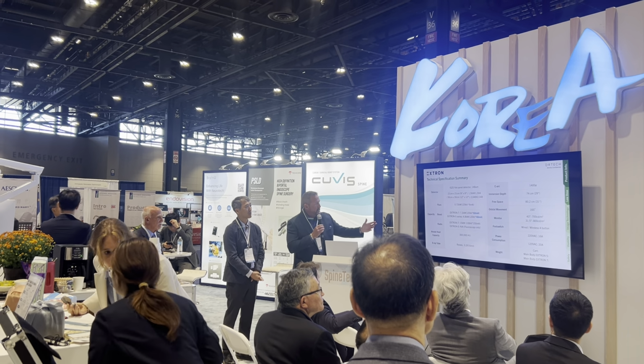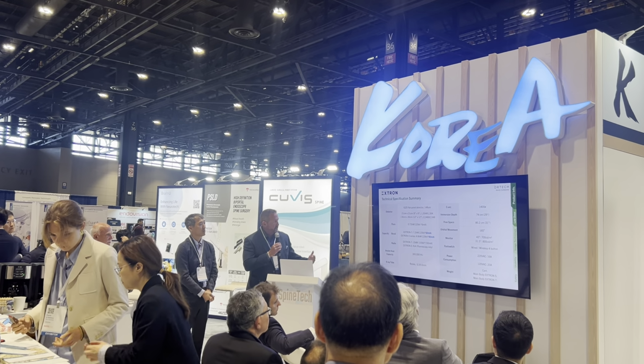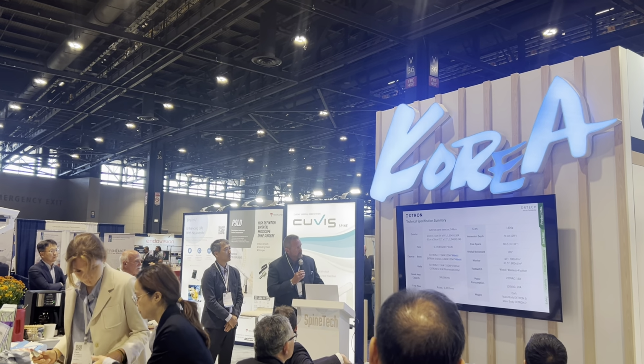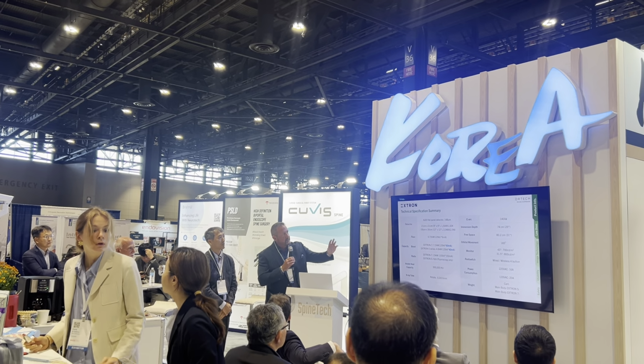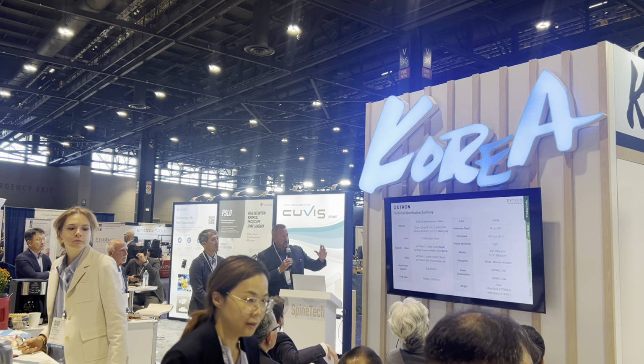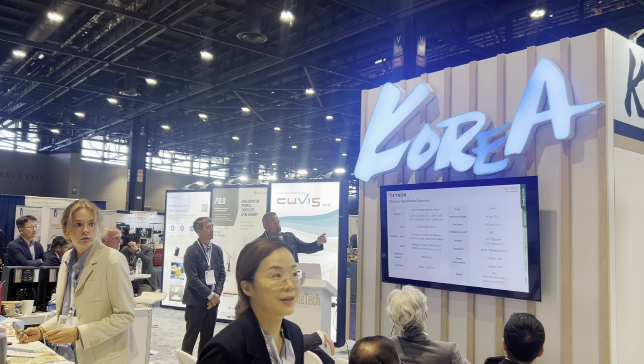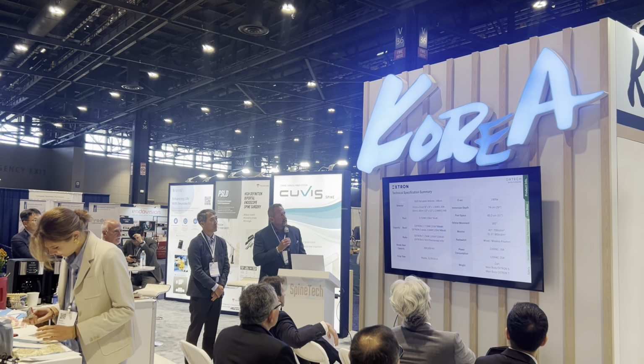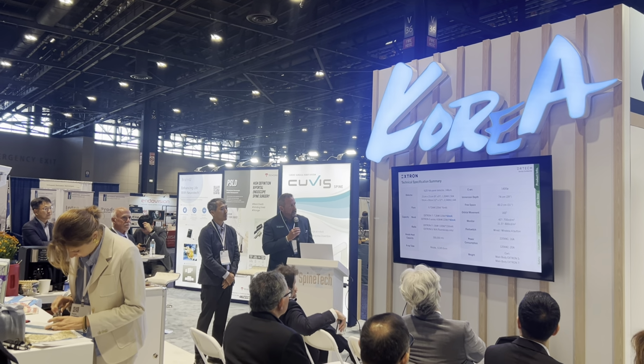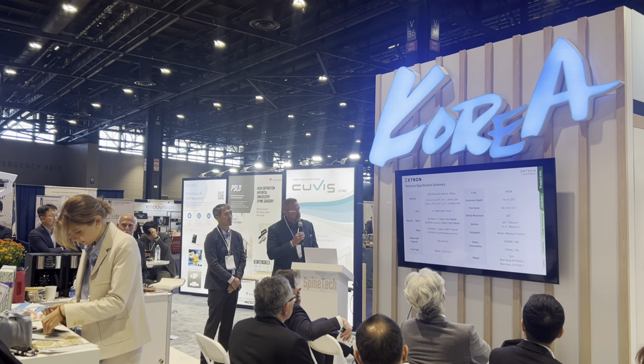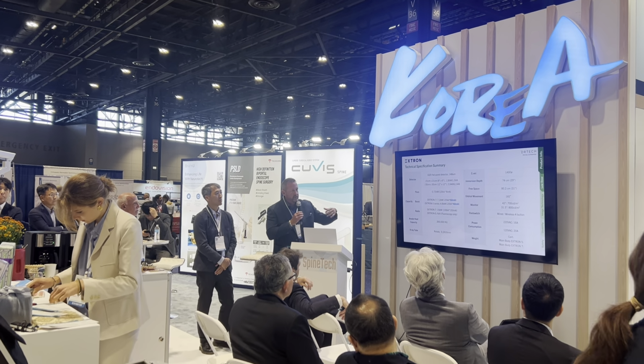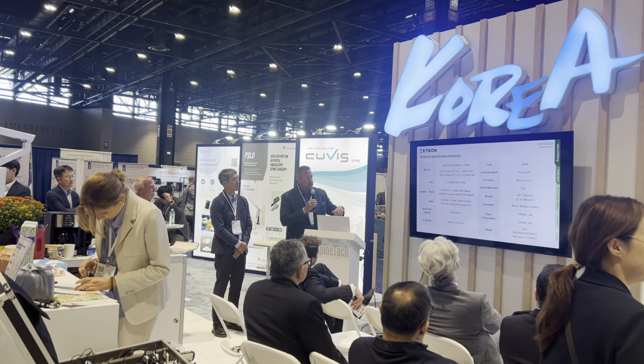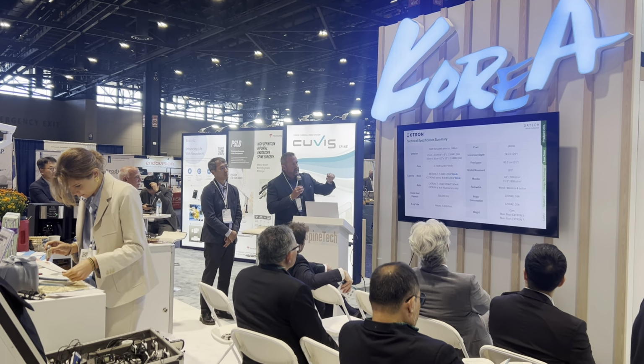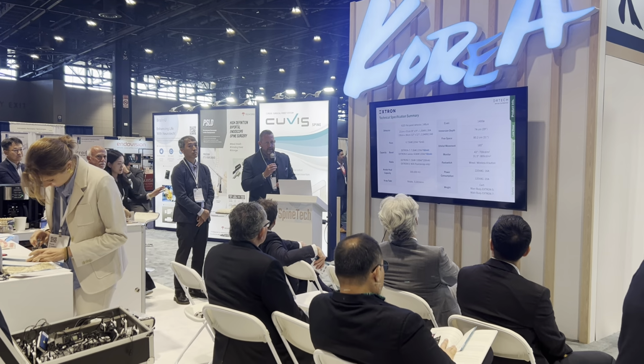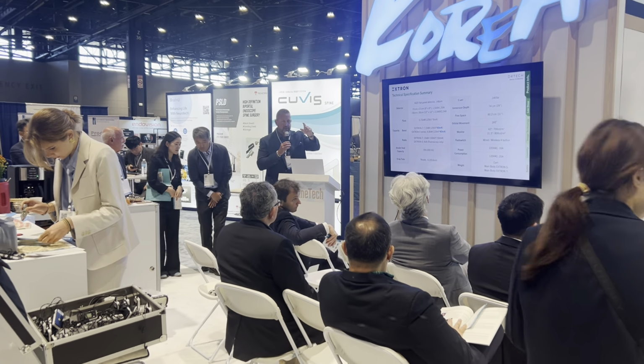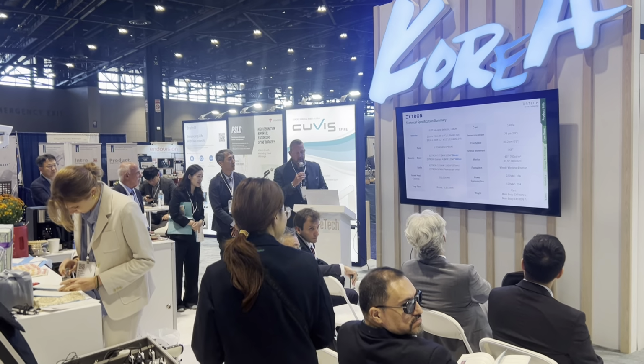300,000 heat units capacity. It's fan cooled. It's a really, really robust system. It's similar to a Super C, if you know what a 9900 Super C is. It has a bigger depth of arc than most C-arms, 29. Free space is 31.5. Again, we talked about some of the movements. There is a wireless foot control. In the US, we're really stocking the wireless foot control with the articulating arm. And again, if anybody wants to do a personalized demo on the system after the presentation, we can walk over to the C-arm and I can show it to you in detail.